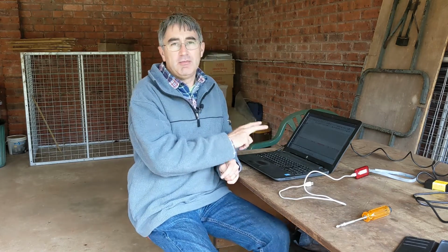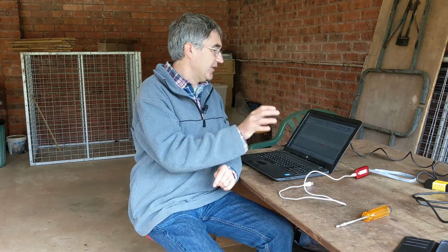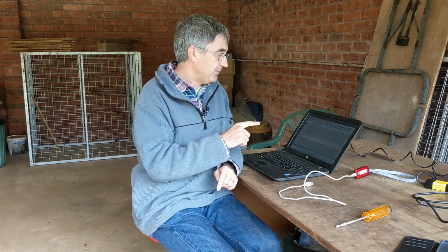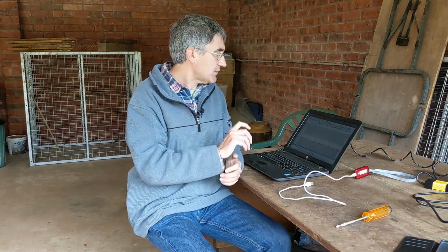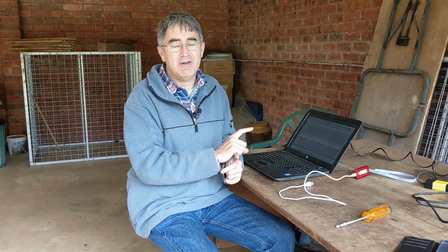When I had the laptop hooked up to the BMS, every 3 seconds it gives me a readout of every BMS module's voltage as reported by the BMS master. The BMS master collects them all up, sends it through to the laptop, as well as doing its own internal error checking. So I could see that some of the data being sent through to the computer was nonsensical. It had values in there that the modules can't transmit, and there was some weird stuff going on.